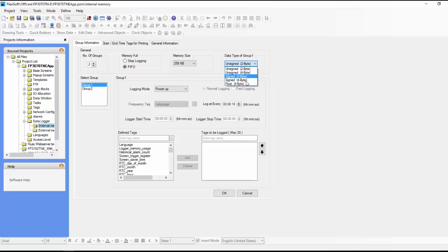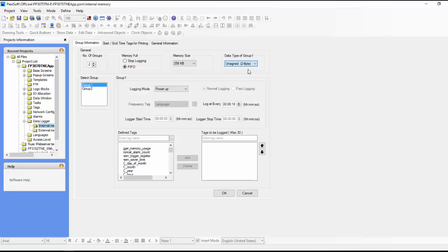You can see we don't have a Boolean data type. So what you do here is have some kind of logic where you have your Boolean. If it's on, you just write one to an unsigned register. If the Boolean is off, then you just write a zero to the unsigned register. So you can create some logic there.